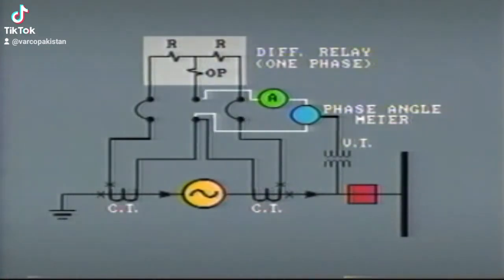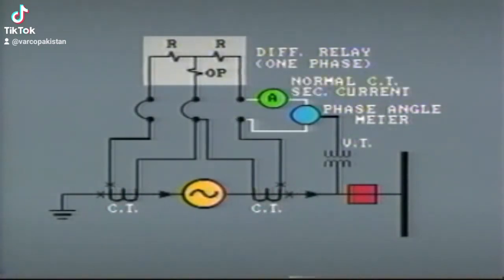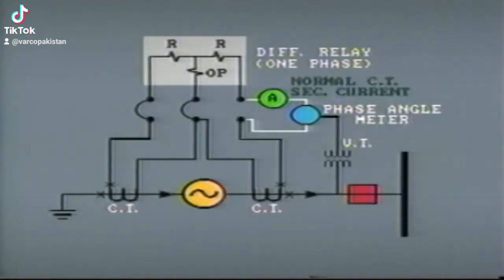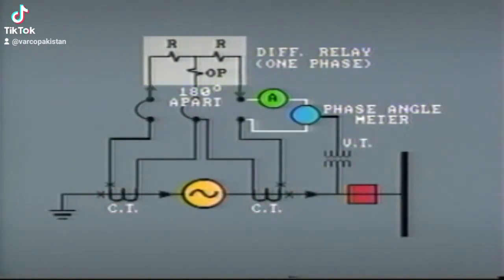With a balanced load on the generator, the current passing through each relay operating coil should be at 0 or a very low value. On the other hand, current measured through the restraint coils should be equal to the CT secondary value. In any particular phase, the current through the restraint coils on either side should be 180 degrees apart. The current enters at one relay terminal and exits from the other. This is correct if there is no internal fault.